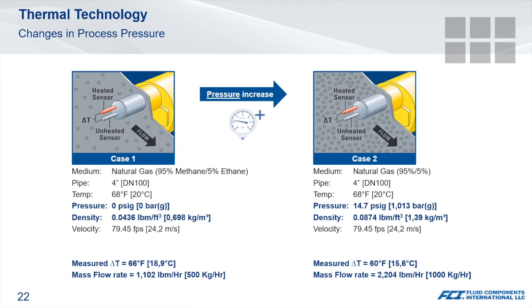To better understand how pressure impacts mass flow, here are a couple of cases that will help illustrate the point. The only difference in the process conditions is the pressure. For case 2, the pressure is doubled. As pressure increases, so does gas density. More gas molecules will take more heat away from the active RTD. The result is the mass flow is increased by a factor of 2. Inversely, decreasing pressures will decrease mass flow.